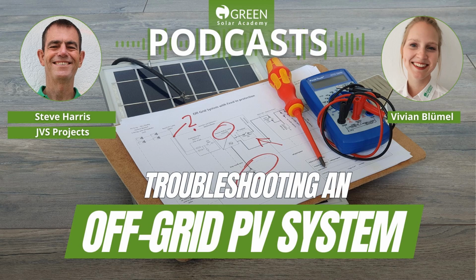I have seen 3 or 4 of these now where the cables have been underrated, and at a bend or at a tight point or something, that heat builds up and builds up and builds up, and suddenly you've got a fire. And you can't stop it, because one of the things that we must understand about a PV generator is while the sun is shining, the generator is running, and you can't switch it off unless you get on the roof and start either disconnecting the things or putting blankets or cardboard or something over the top of the panels. And when you've got 18 or 20 panels on a roof, it's quite hard to switch it all off. Use the right cable.